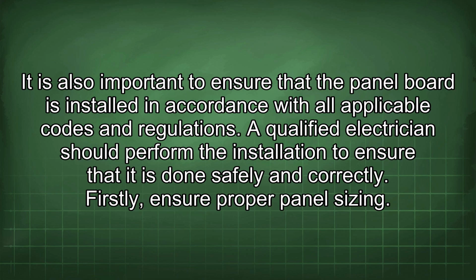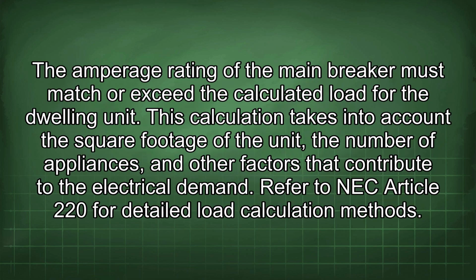Firstly, ensure proper panel sizing. The amperage rating of the main breaker must match or exceed the calculated load for the dwelling unit. This calculation takes into account the square footage of the unit, the number of appliances, and other factors that contribute to the electrical demand. Refer to NEC Article 220 for detailed load calculation methods.